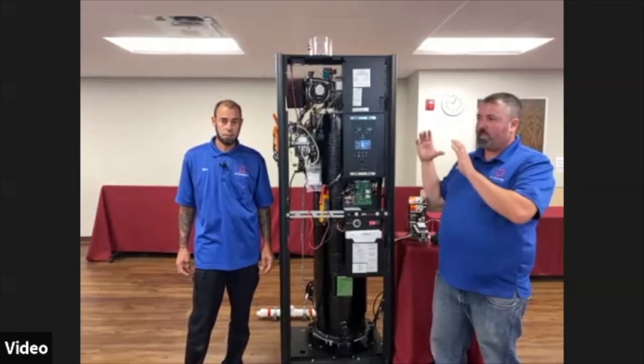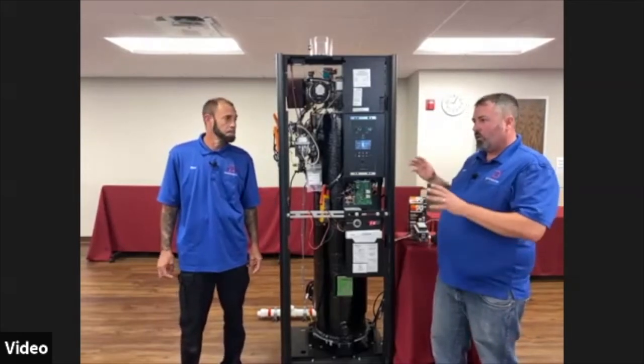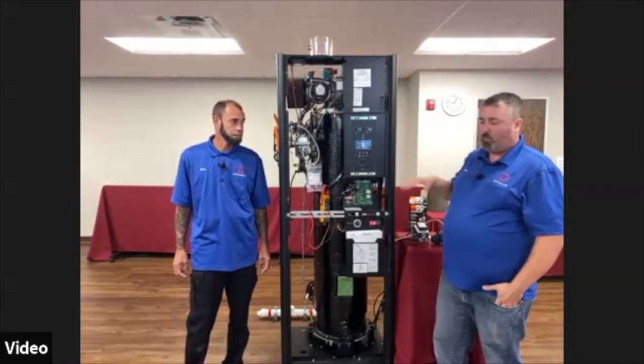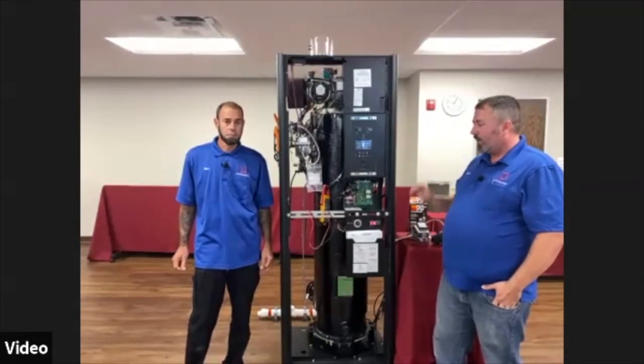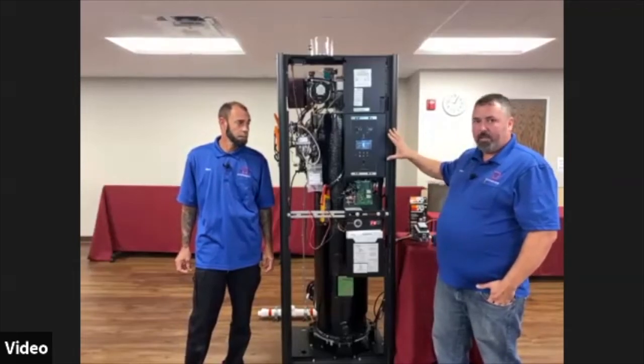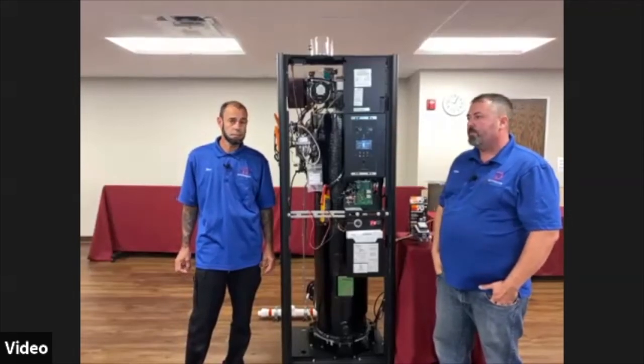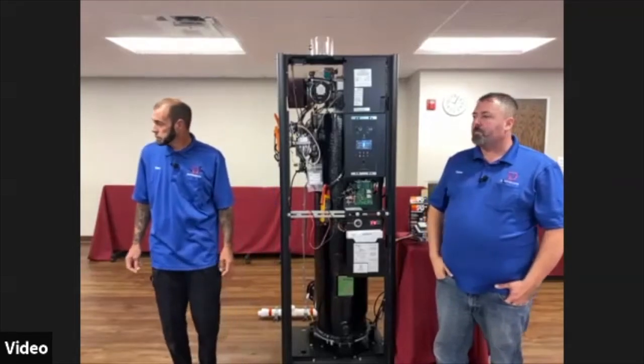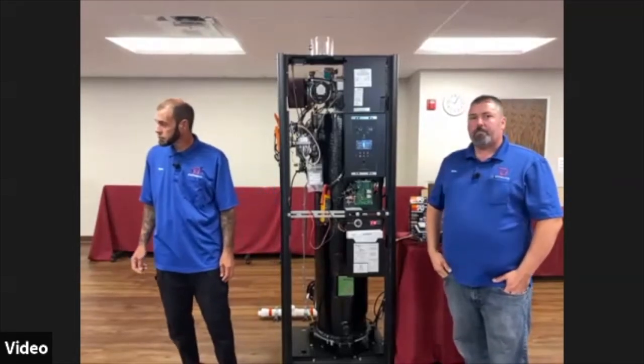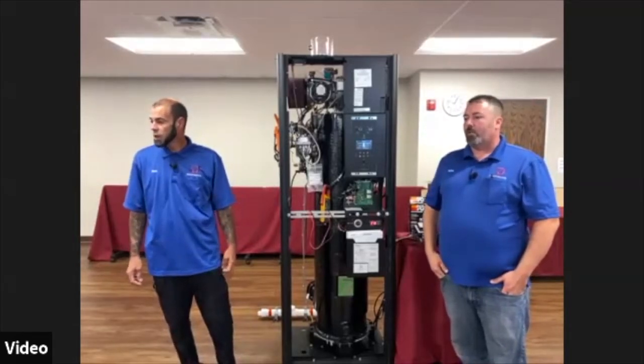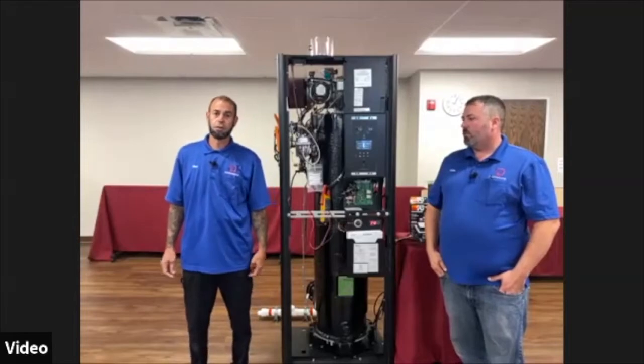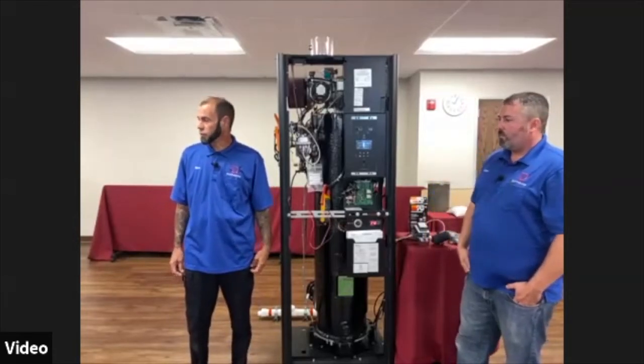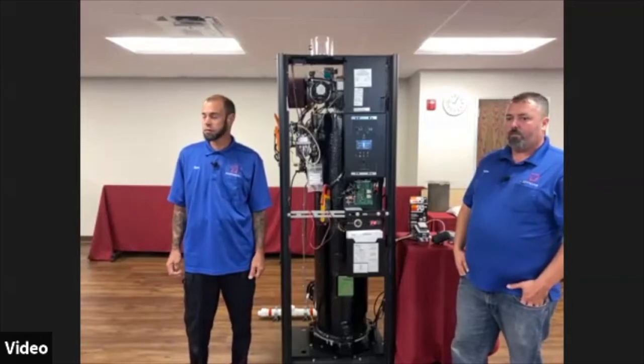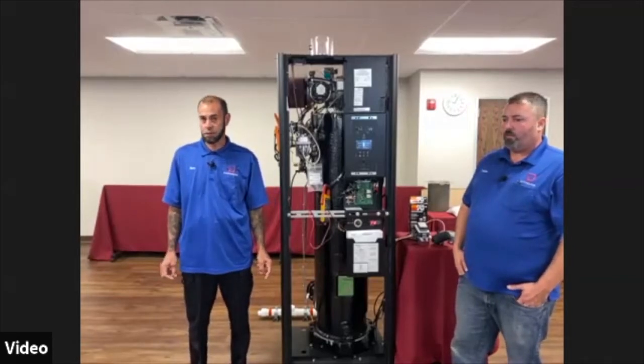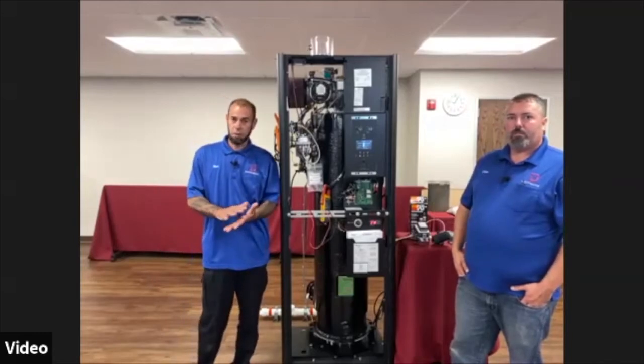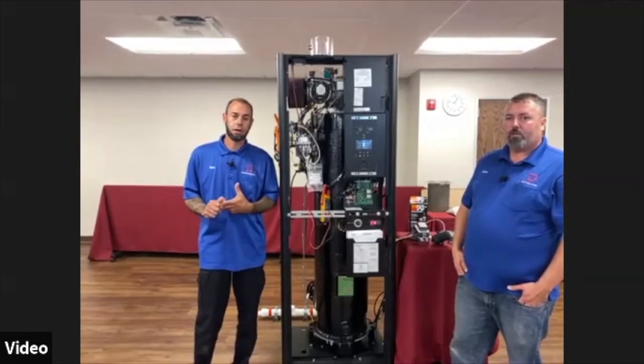You would need to possibly mount an ACS control, which will be an external control that will sequence the boilers much like BST. You don't get quite the added stuff you get out of the BST system, but it works very similarly. Okay, thank you. Our next question is, does AERCO make the Benchmark in a dual fuel option? The answer to that is yes, they do. So they make it in a dual fuel above 1 million BTUs, propane and natural gas. For anything above 1 million BTUs. The 750 and the 1 million are not dual fuel.